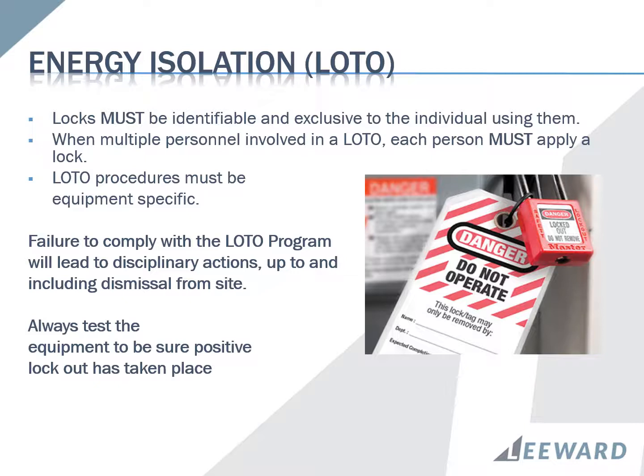Energy isolation. Locks must be identifiable and exclusive to the individual using them. When multiple personnel are involved in a LOTO, each person must apply a lock. Lockout-tagout procedures must be equipment specific. Failure to comply with the lockout-tagout program will lead to disciplinary actions up to and including dismissal from site. Always test the equipment to be sure positive lockout has taken place.